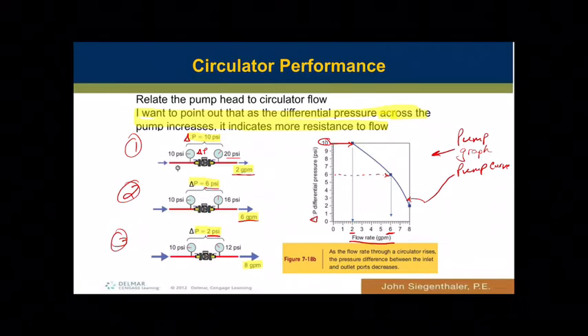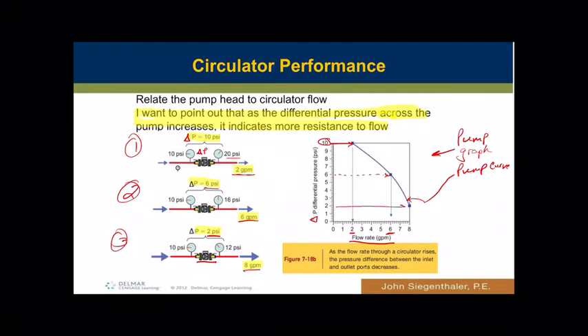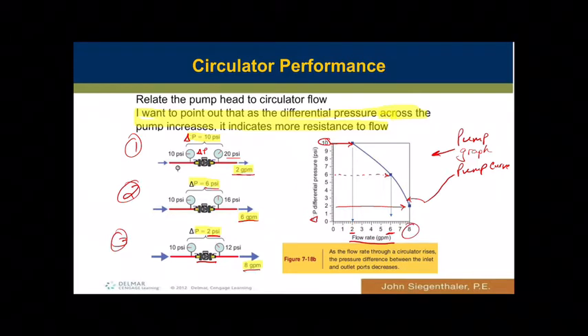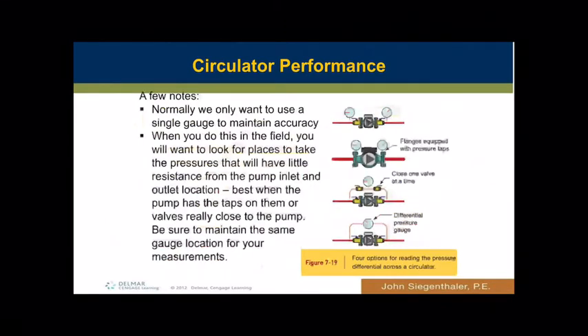The third example has much lower resistance — only a 2 PSI differential. Most of our pumps are single-speed pumps, so when the pump is energized it runs at a fixed speed. At delta P of 2 PSI, we go straight across the curve and find that represents 8 GPM. That's essentially how to relate the flow of a pump, the delta P, and how that relates to flow — every system is different and unique.